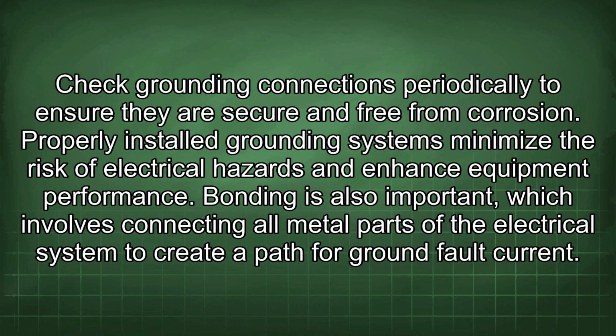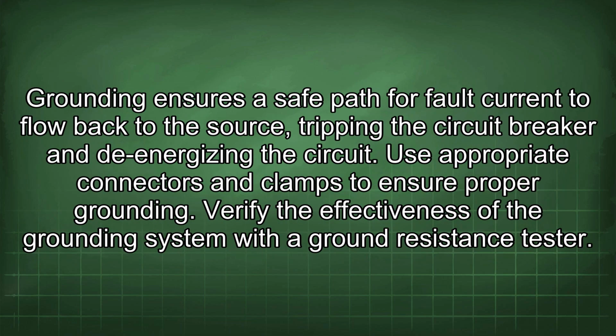Check grounding connections periodically to ensure they are secure and free from corrosion. Properly installed grounding systems minimize the risk of electrical hazards and enhance equipment performance. Bonding is also important, which involves connecting all metal parts of the electrical system to create a path for ground fault current. Grounding ensures a safe path for fault current to flow back to the source, tripping the circuit breaker and de-energizing the circuit. Use appropriate connectors and clamps to ensure proper grounding.